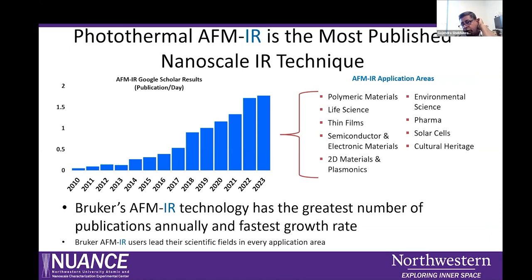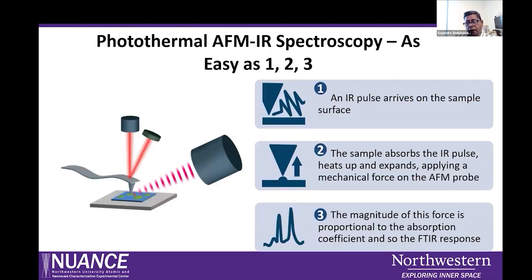Since the NanoIR has been on the market, this is one of the advertising slides from Bruker. Publications are coming almost every day, and this system has been installed at a few different locations. Most of the applications are polymers, life science, thin films, semiconductors, 2D materials, and plasmonics. So we are not limited to a very specific sample preparation. As long as the AFM can get a nice topography image, we can get an IR spectrum. But unfortunately, we cannot do liquids, so that is one of the limitations here. In the case of photothermal AFM-IR spectroscopy, an IR pulse arrives at the sample surface, and the sample absorbs that, heats up and expands.